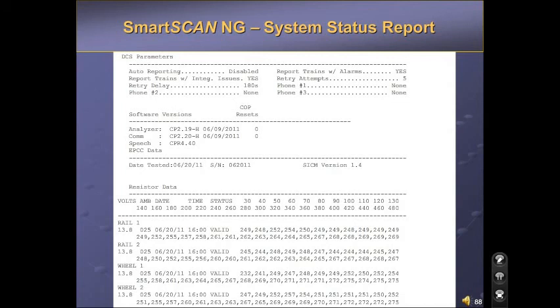It does not contain as many samples as the table. Checking scanner information, average heats, and resistors read on the train detail report can help determine if the scanner needs to be replaced. Pending means that the test is yet to be run. If the system has a train passing through the location before the resistor table has been run, the detector will use the interim test on that train and will restart the 20-minute counter. After 20 minutes, it will run the resistor table.